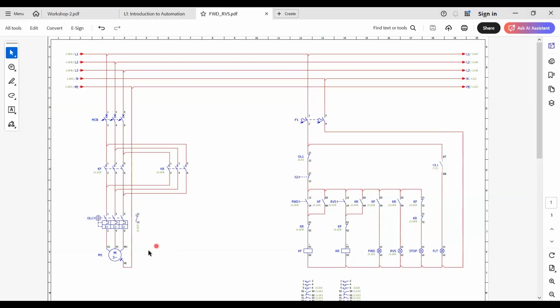Now assume like there's an overload event due to heavy loading of the motor. This overload may trigger. So in that case, the current comes here. This will trip, or then this normally closed contact will open. That will de-energize all power to all the light indicators and the coils, power coils of the forward and reverse. But it will display the yellow lamp or the fault lamp to the user by using the normally open contact of this overload relay.